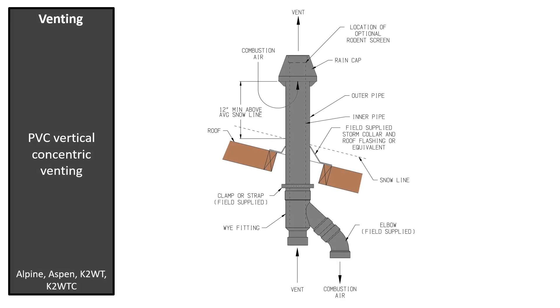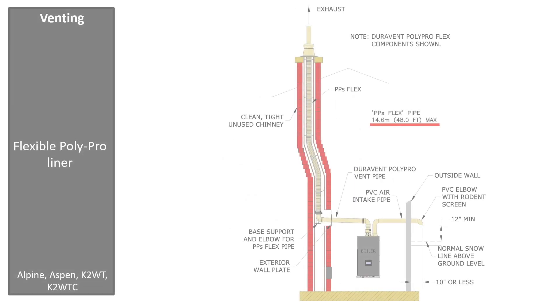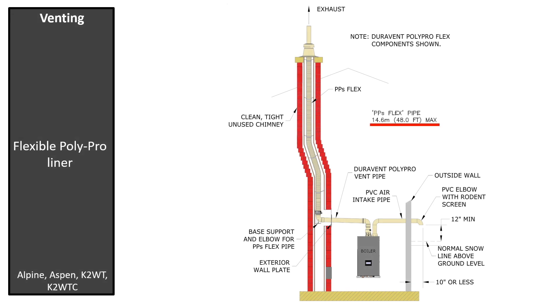PVC concentric vertical venting should be a minimum of 12 inches above average snow level. If using the existing chimney for venting, apply either a polypropylene or stainless steel flexible liner and use the sidewall for air intake. To determine the equivalent pipe length of a flexible liner, multiply the length of the liner by 1.2. Unlike using existing B vent, combustion air cannot be drawn from masonry chimneys. Refer to the I&O manual for manufacturer part numbers.